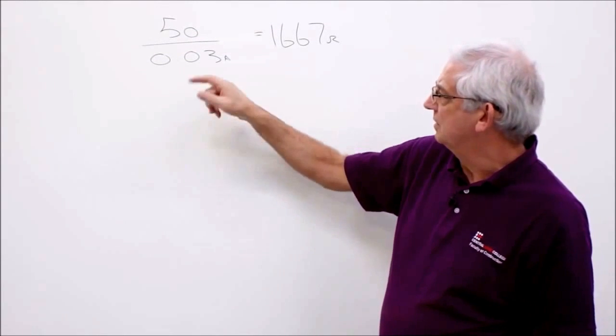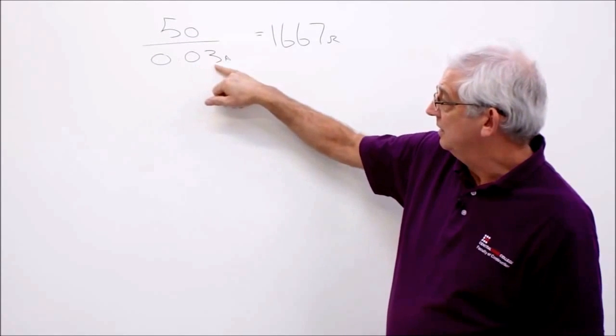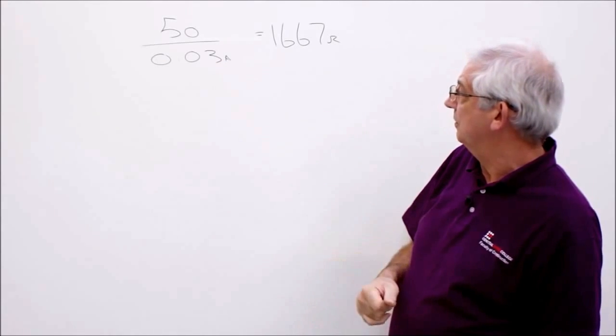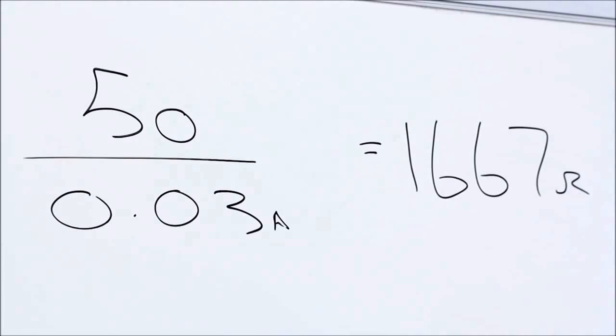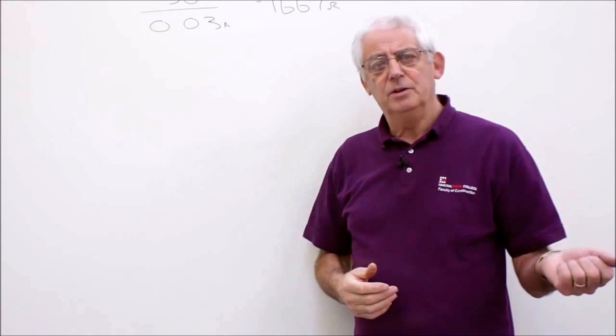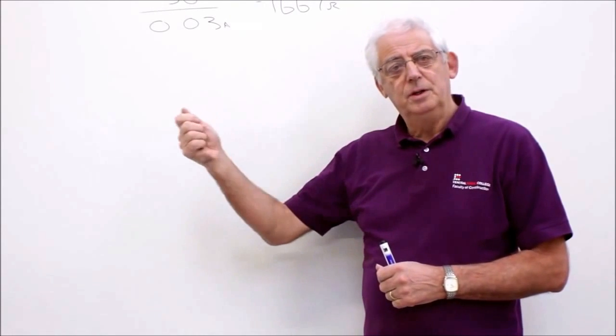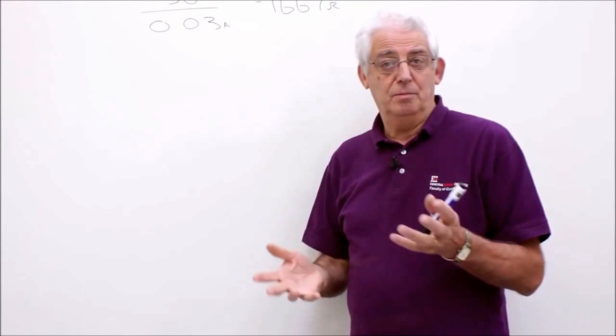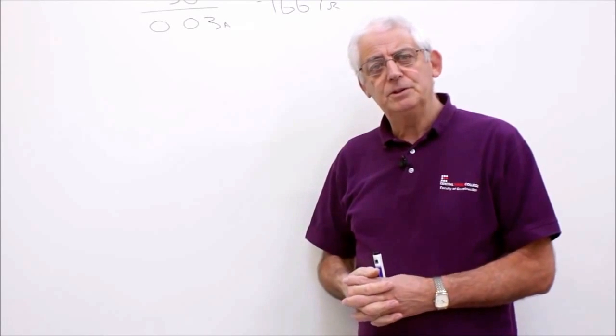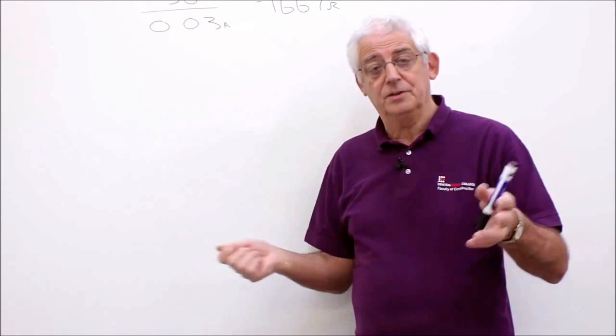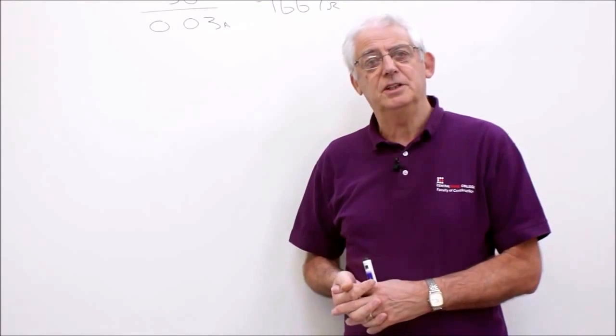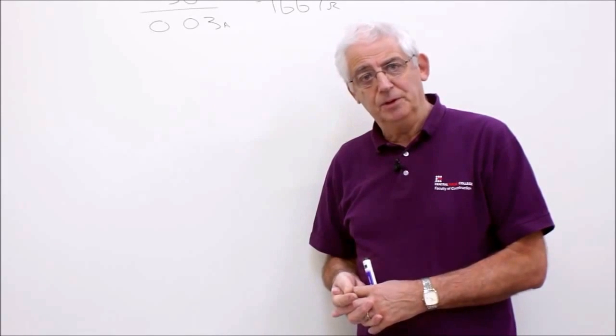Okay, so I delta N in this case for a 30 milliamp RCD is 0.03. If we divide that into 50, it gives us a value of 1,667 ohms. So the measurement we need to take really is between a known earth within the room, if possible, to whatever piece of metal we think may or may not need bonding. If the resistance between the earth and the piece of metal is less than 1,667 ohms, it doesn't need bonding. It's considered that that resistance is low enough. If it's above 1,667 ohms, then it does require bonding.